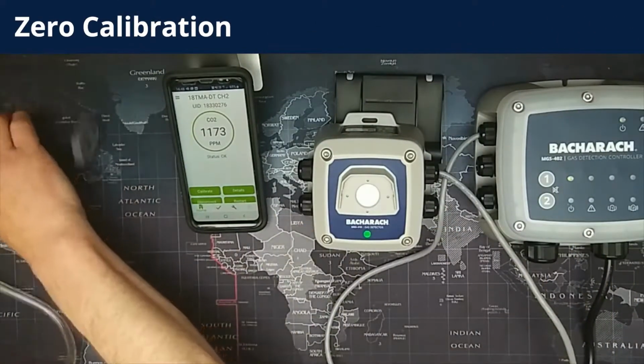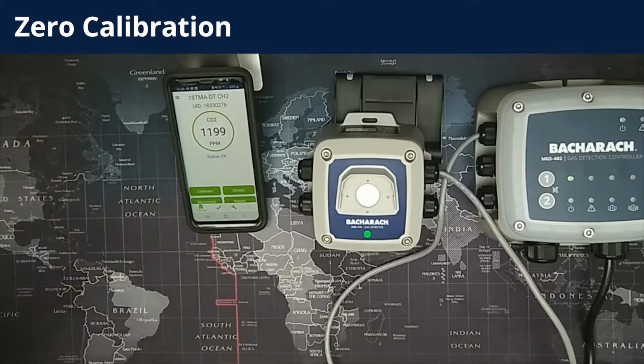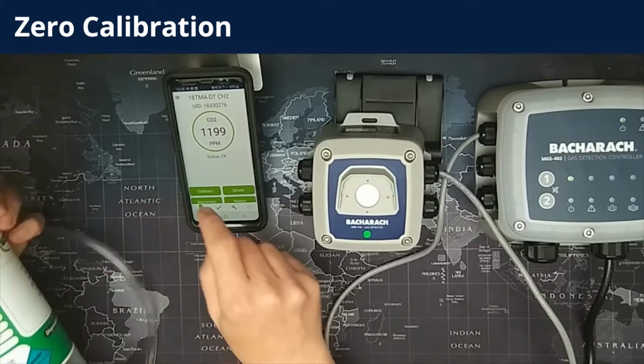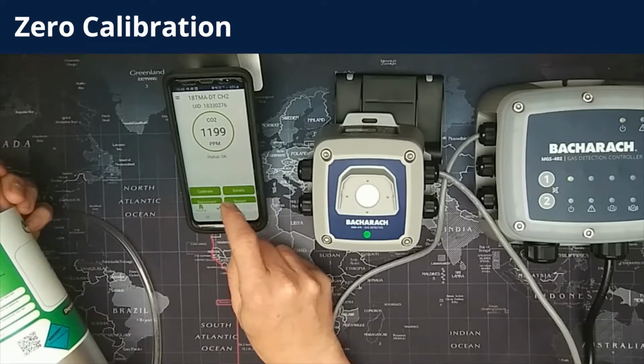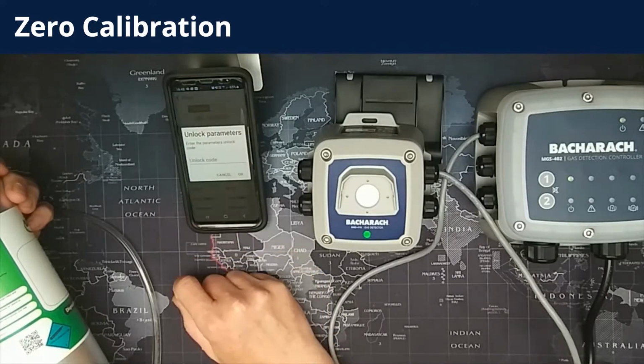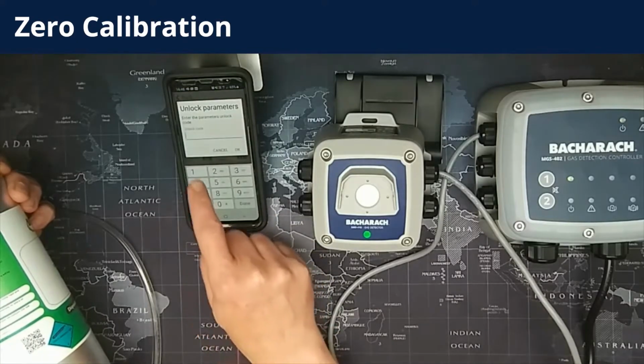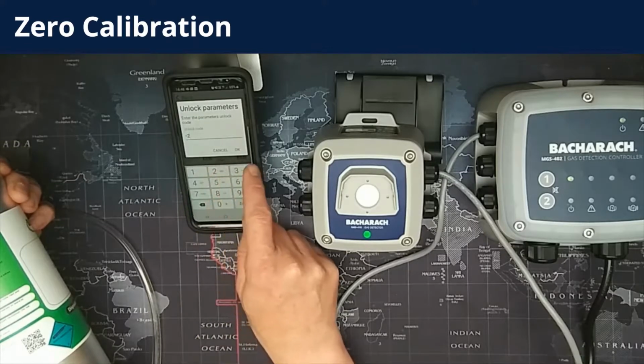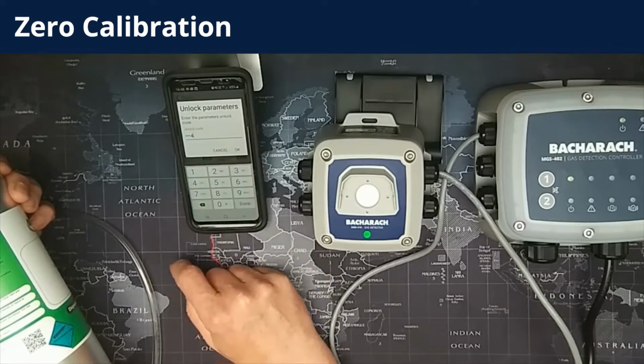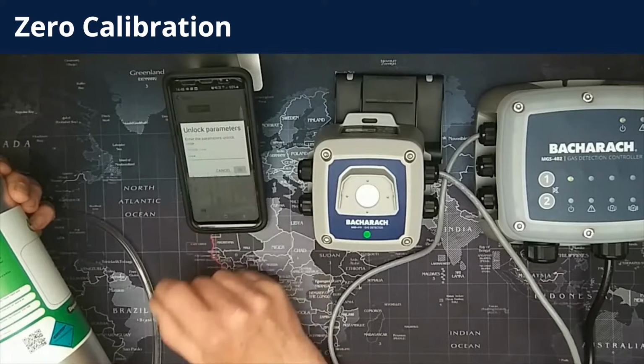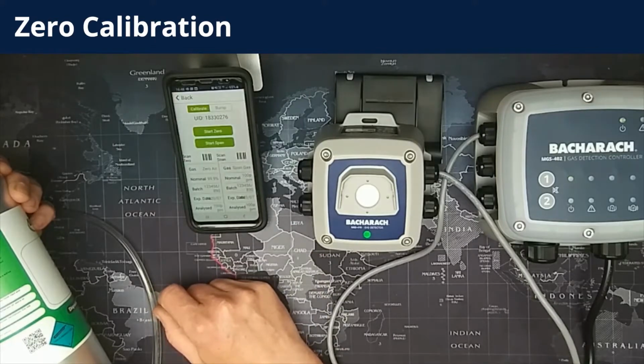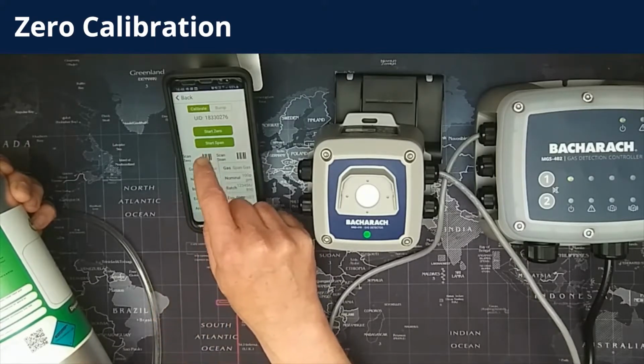Now we move on to zero calibration. The first thing you need to do is to select Calibrate from the main screen. That'll take you to the Unlock Code Entry screen. The default unlock code is 1234. It won't let you enter any more than 4 digits. Once that has been entered, it will take you to the calibration screen.